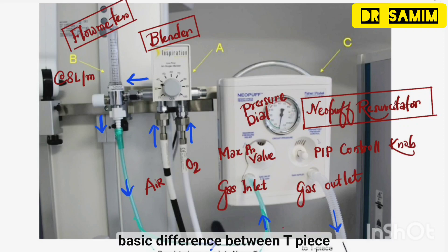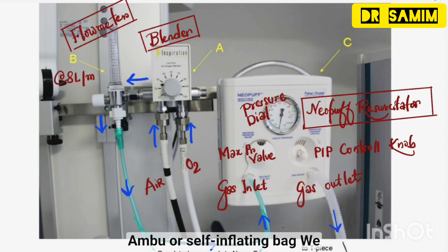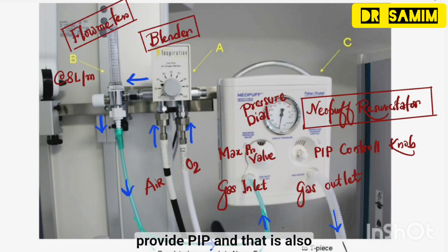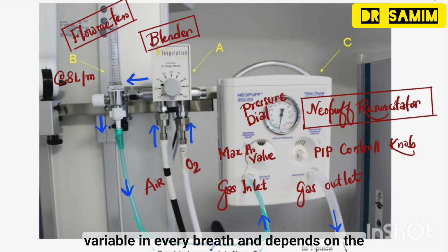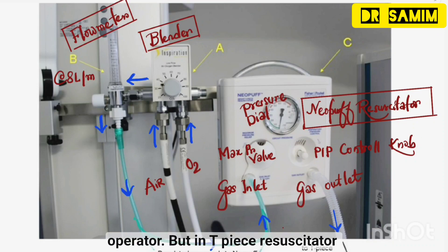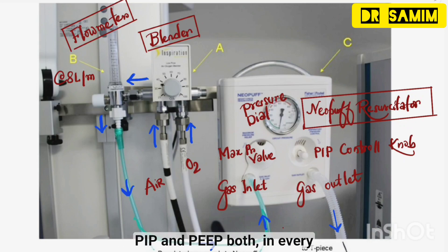What is the basic difference between the T-piece resuscitator and AMBU? In AMBU, or self-inflating bag, we cannot provide PEEP — only PIP, and that is also variable in every breath and depends on the operator. But in the T-piece resuscitator, we can provide preset PIP and PEEP both in every breath, so there is less injury to the airway.